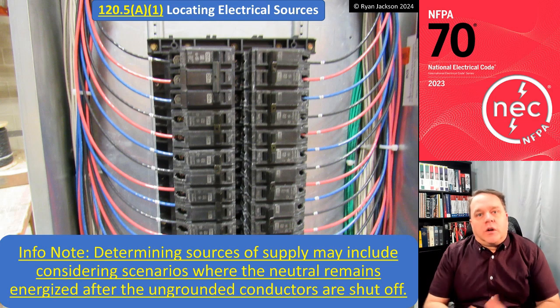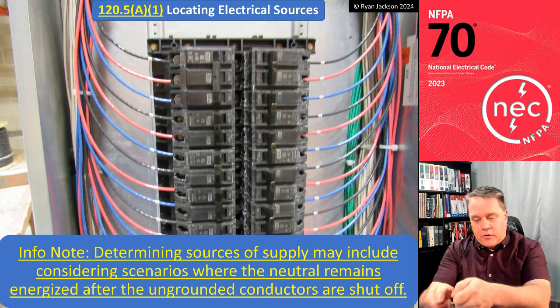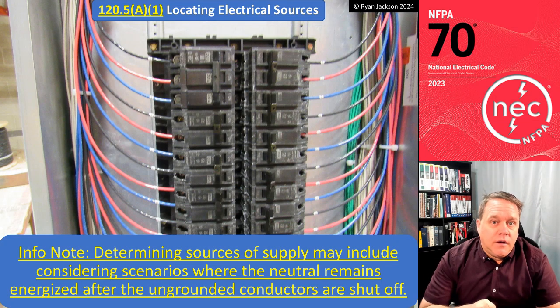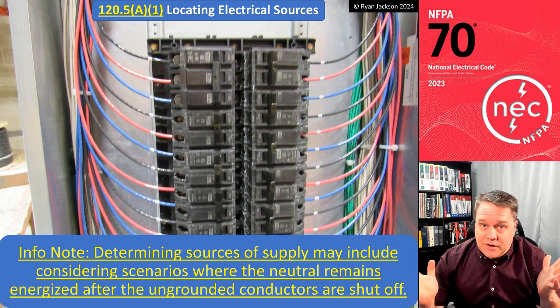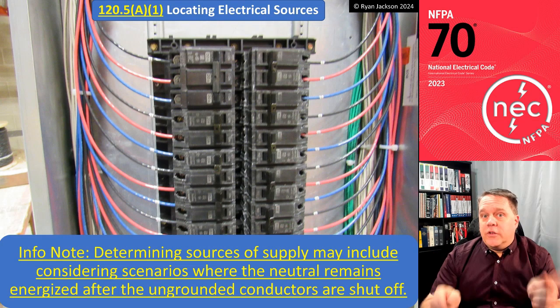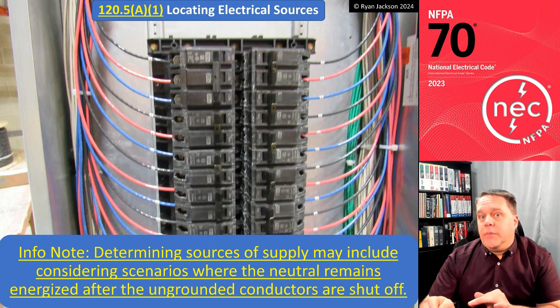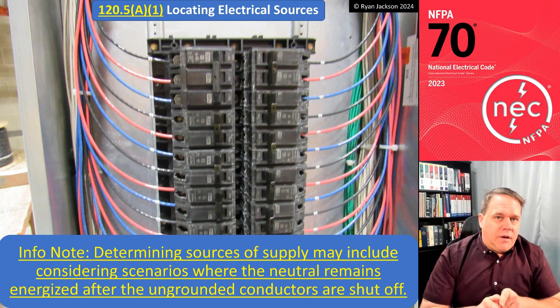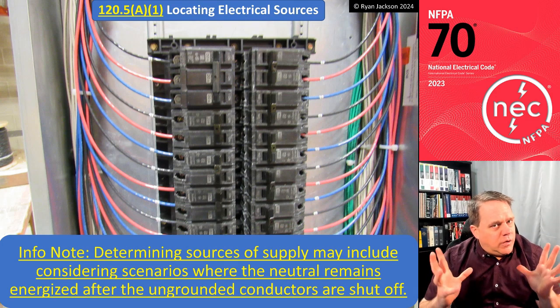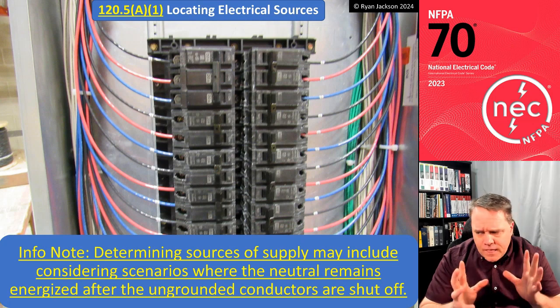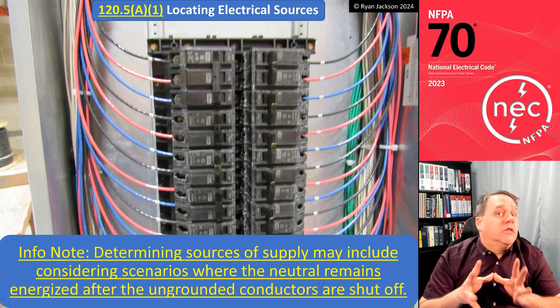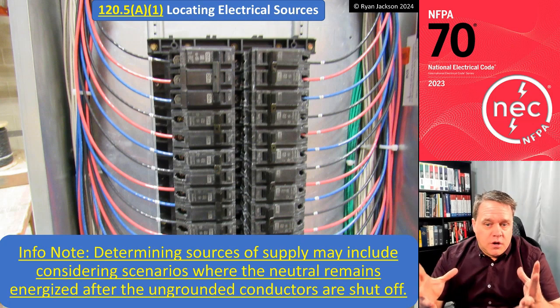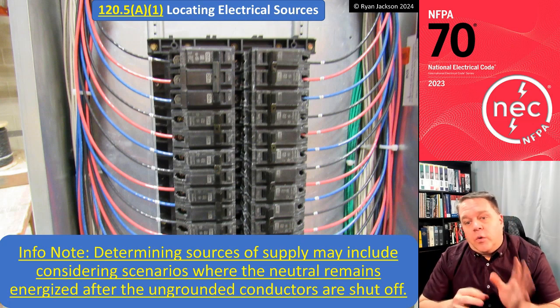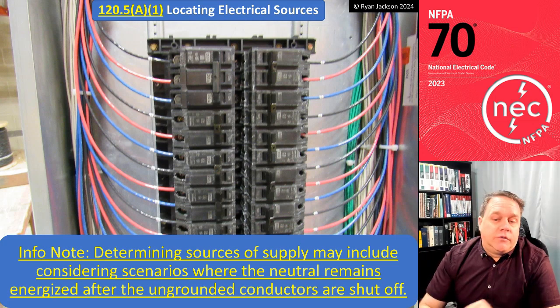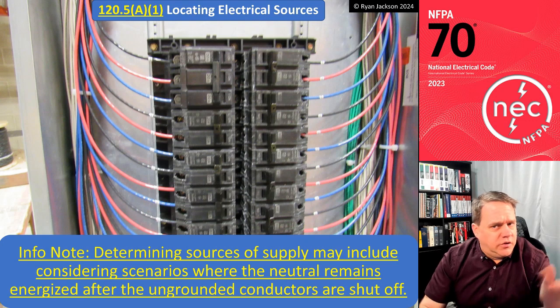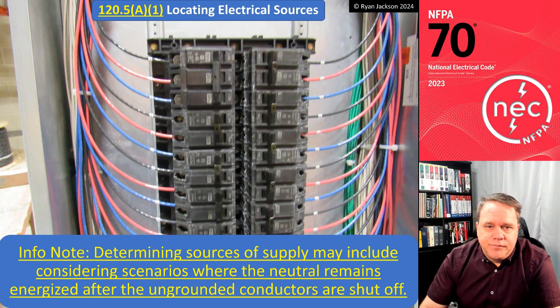And if you're working on a piece of equipment and you're working on circuit 1, you shut off circuit 1, well, that doesn't mean you shut off circuit 41 and 16. So the neutral conductor for those 3 could still be energized. So the informational note doesn't really tell you what to do or how to do it. It just says, listen, determining the sources of voltage might include considering scenarios where the neutral remains energized after the ungrounded conductors are shut off. So just something to keep in mind.